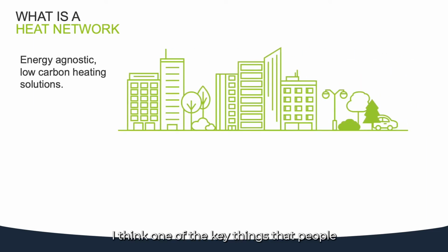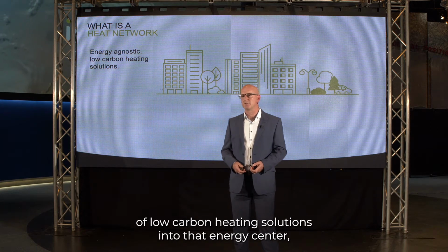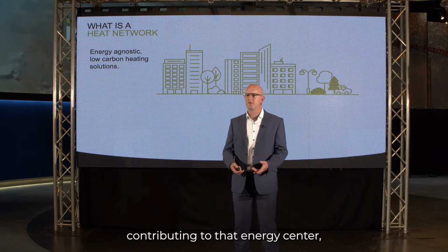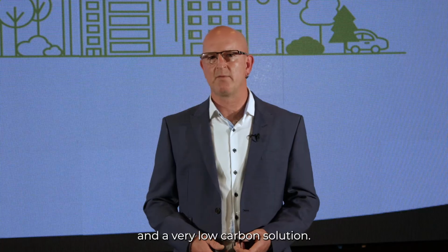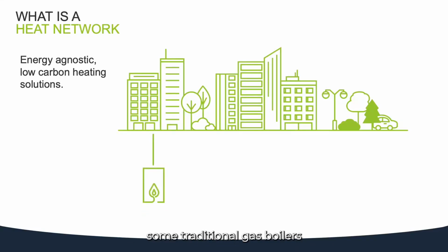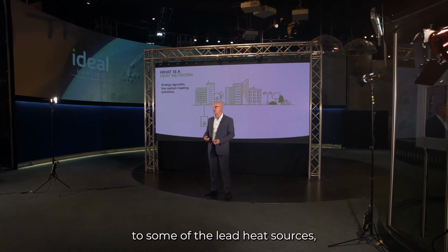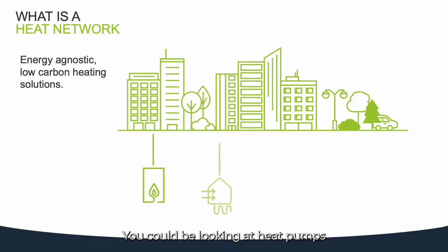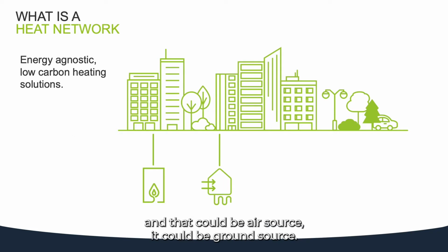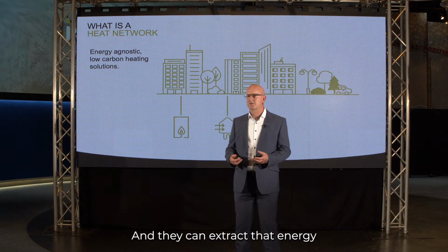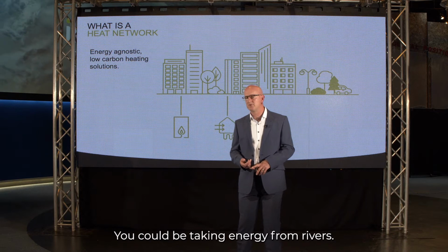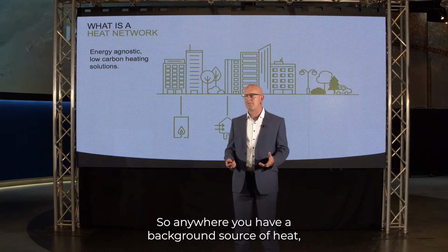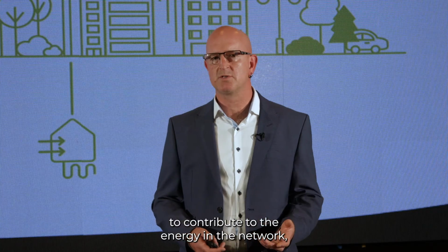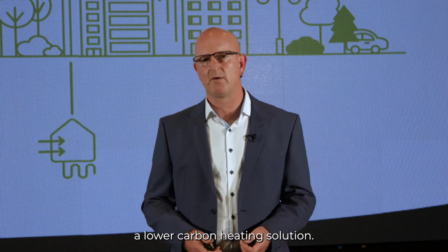When we talk about heat networks, I think one of the key things that people will often bring into the conversation is the fact that they are energy agnostic. You can incorporate a number of low carbon heating solutions into that energy centre, or you can have low carbon energy solutions contributing to that energy centre to give you overall a very efficient and very low carbon solution. In the first instance, you could have some traditional gas boilers until the technologies are more widely available or more widely used. The gas boilers could be providing backup to some of the lead heat sources, which are low carbon heat solutions. You could be looking at heat pumps, and that could be air source, ground source, or water to water heat pumps, and they can extract that energy from a number of different sources. You could be taking energy from rivers, or from mine water. So anywhere you have a background source of heat which you can run through that heat pump to contribute to the energy in the network, you have an opportunity to realise a lower carbon heating solution.